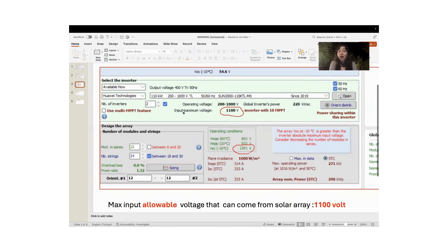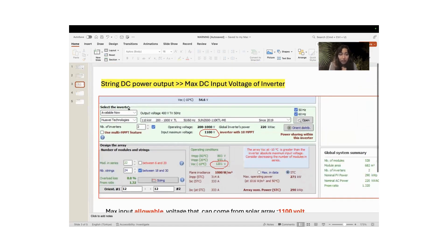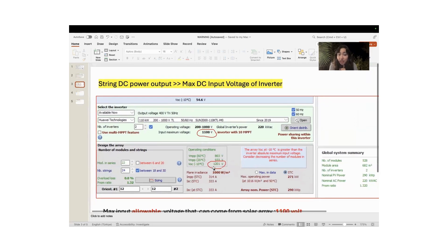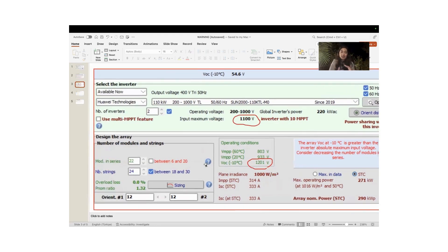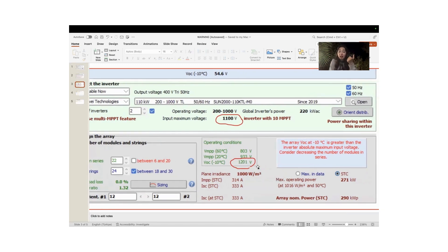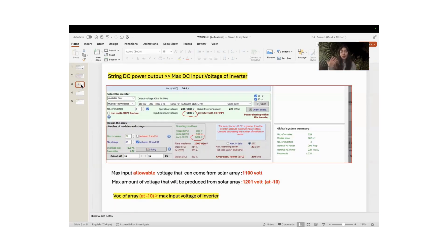When we go to the inverter section, the maximum input voltage is 1100 V, but the voltage attained at minus 10°C is 1200 V. So when we increase the number of modules from 20 to 22, the open-circuit voltage at minus 10°C exceeds the inverter's maximum input voltage.